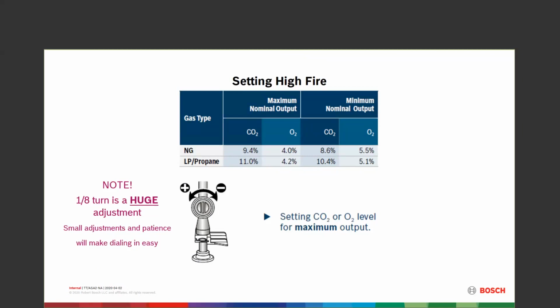So the biggest thing on this is to be patient when you're doing your testing, going from low fire to high fire and high fire to low fire. Take little adjustments. Get your values moving in the correct direction. So get your CO2, let's say in low fire. I'll give you an example. Low fire, you're at 8%. You're going to increase gas and get it going toward 10.4. Don't take it all. So you might start at 8, get it to move to 9.